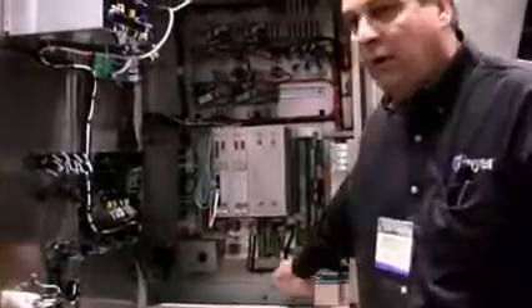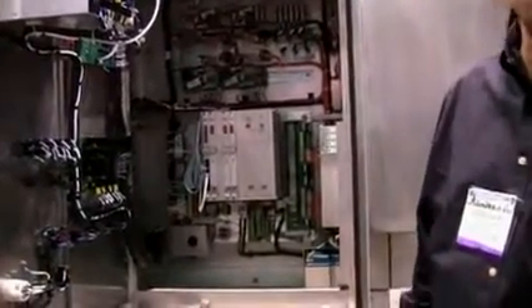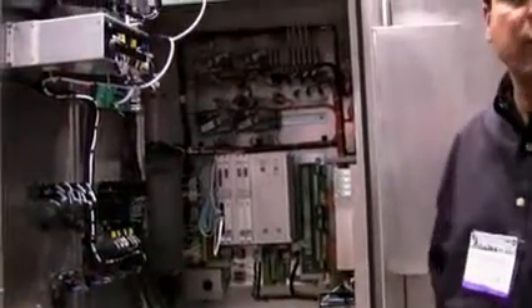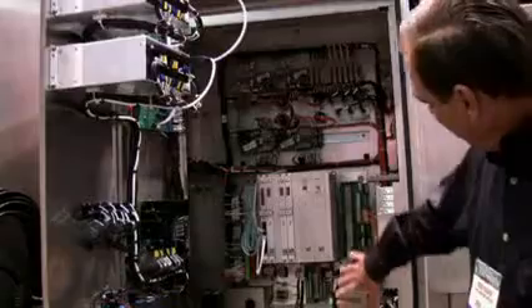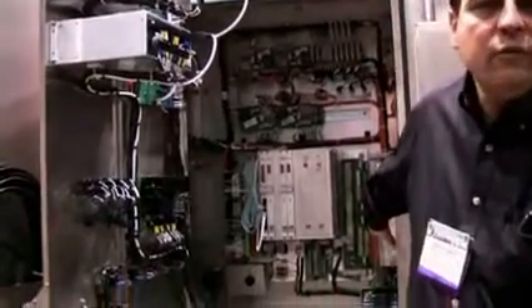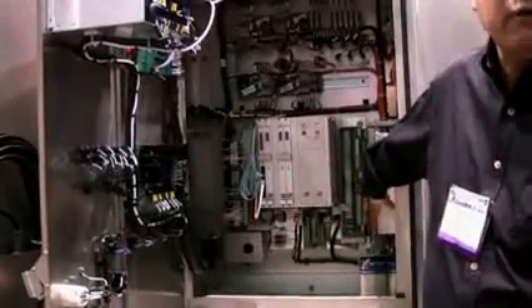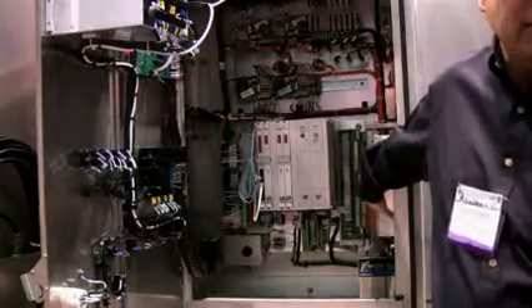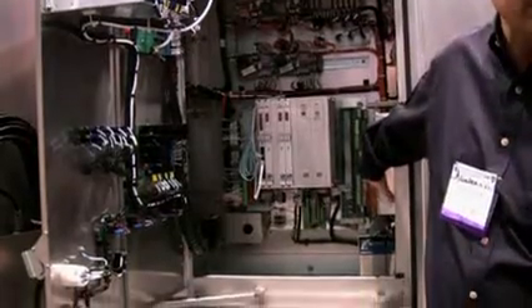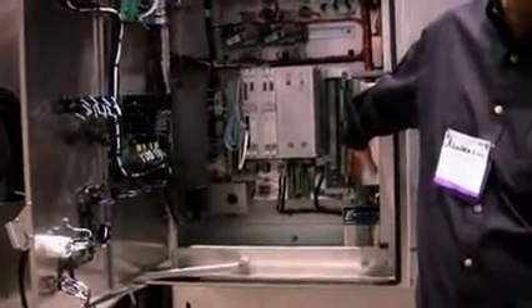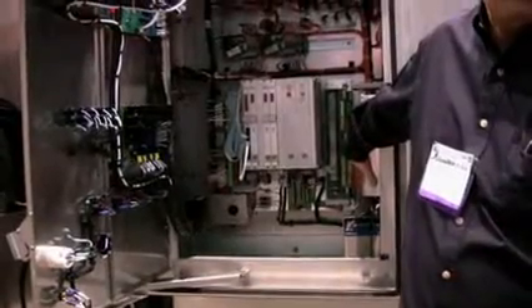We have batteries in here. Battery backup on this particular unit is 8 hours. We go up to 24 hours backup on our units when we go to bigger batteries. This particular unit has a 10 amp power supply in it. This power supply will run the unit without the batteries and will operate it fully. So if we have dead batteries, we're still operational as long as we have AC power available.